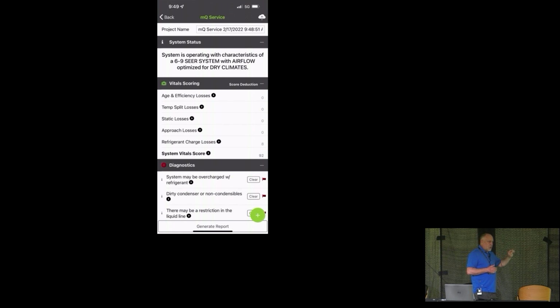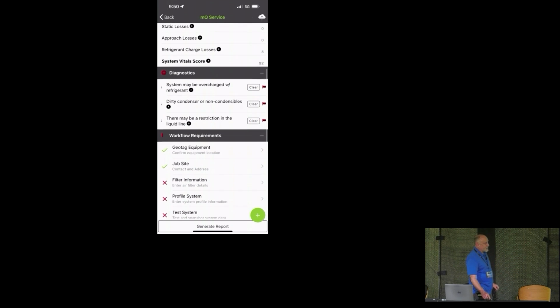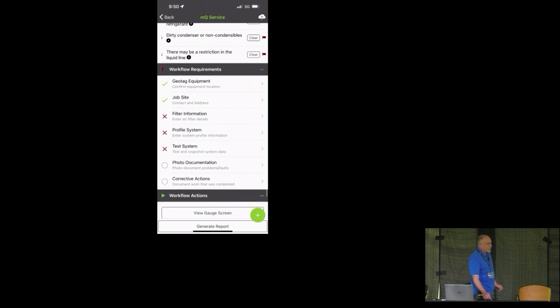But every one of those elements is based upon all of our industry studies. So there's probably about 13 algorithms running in the background that are taking into account your approach, your static pressure losses, your temperature split losses, age and efficiency losses, refrigerant charge losses. Refrigerant charge, believe it or not, has less of an impact than anything on there, especially a slight overcharge, but that's what's causing the high head pressure on the machine. It's also doing your diagnostics. So what we're doing is taking you into scoring the system, the diagnostics on the system, and then this part of the project becomes secondary.